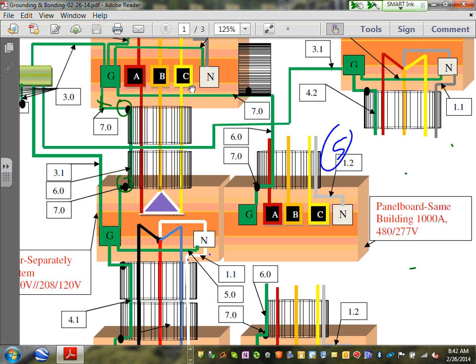Okay, the second thing you need to do, right at the transformer, is you have to have a grounding electrode conductor. That's this guy, guys. A grounding electrode conductor from the transformer all the way to the grounding electrode system. Guys, almost all transformers are called a separately derived system. The reason they call it a separately derived system is, can you see the delta? Everybody can see the delta here. Maybe this is not a good choice. The delta and the Y are completely separated from each other.